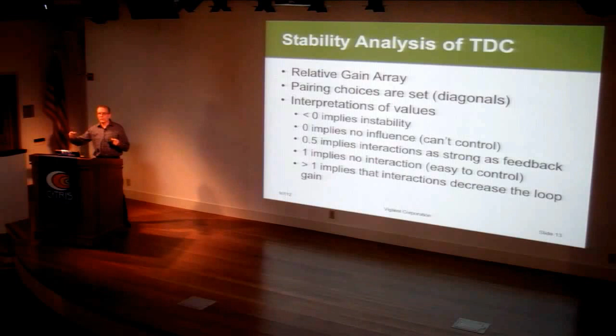And the way you interpret this array is that if you get values less than 0 on any of the diagonals, that means the system is going to be unstable in one way or another. If it's 0, it implies there's no influence of that control on that actuator. If it's 50%, it implies that the interactions are about as strong as the loop feedback for that control loop. If it's 1, it implies there's no interaction, so this is what you'd like to have, nice and easy to control. And if it's greater than 1, it means the interactions decrease the loop gain. So as it gets greater and greater, it gradually gets harder and harder for that loop to be controlled.